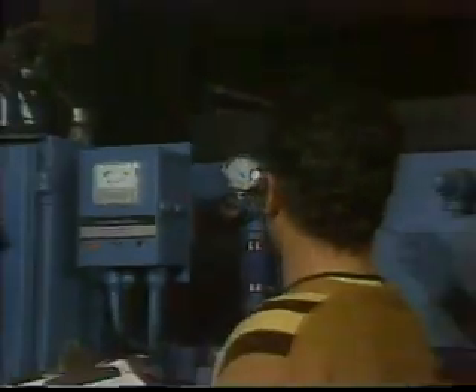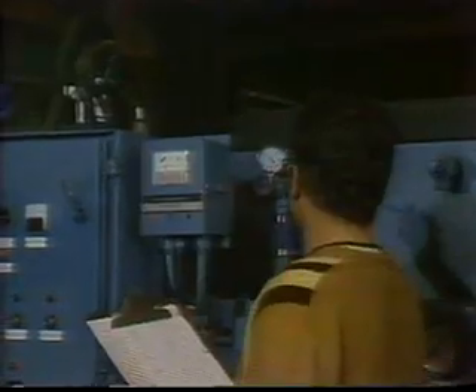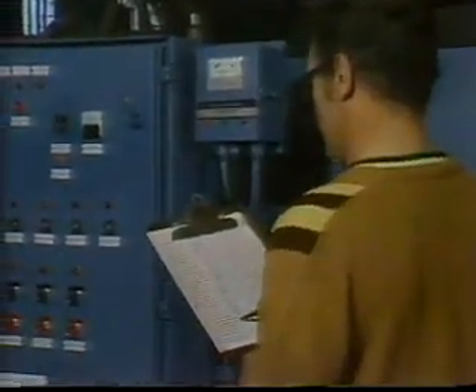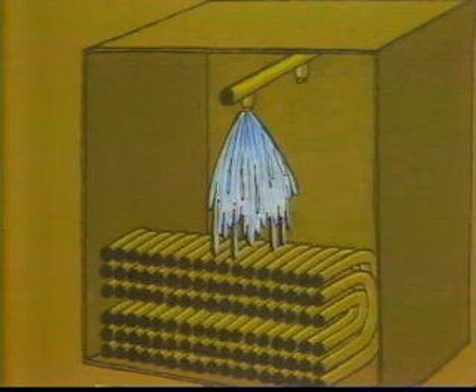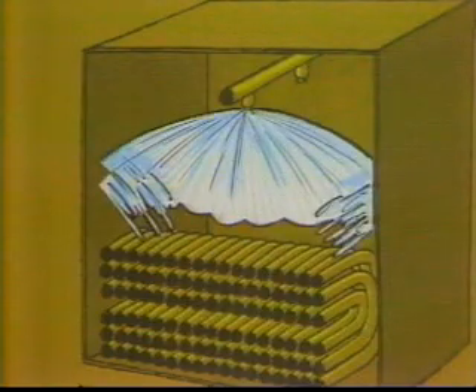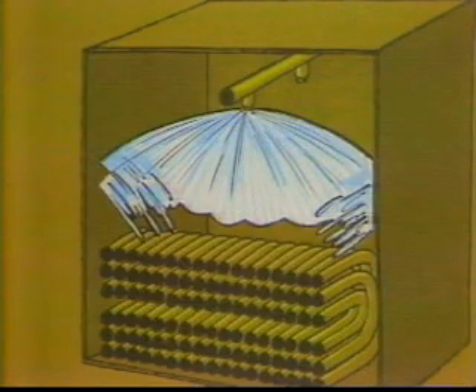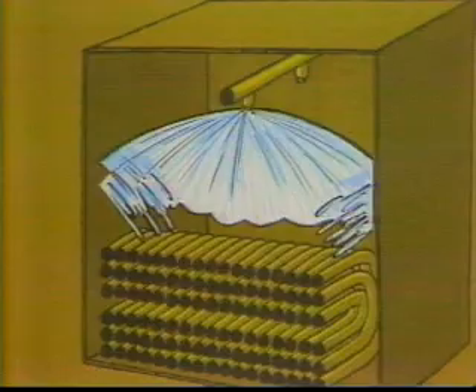Spray nozzle pressure is read from this gauge and will run between 5 and 9 psig. This one's reading 9. A low pressure will cause narrowing of the spray nozzle pattern, which results in reduced distillate output and rapid scale formation. Pressure above 9 psig results in a widening of the spray pattern, causing water to be sprayed on the walls of the unit rather than on the bundle. This causes a loss of distillate production and a more rapid buildup of scaling.